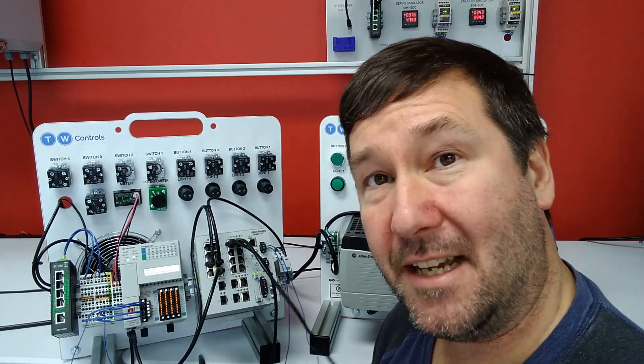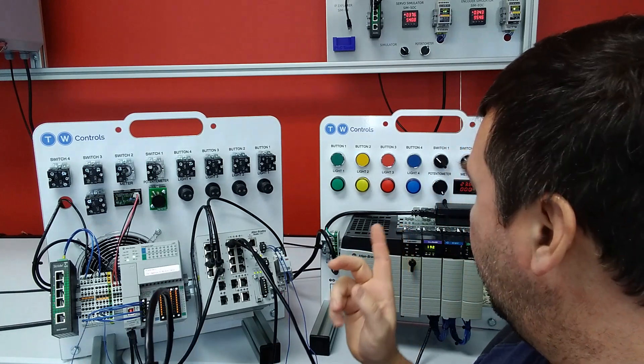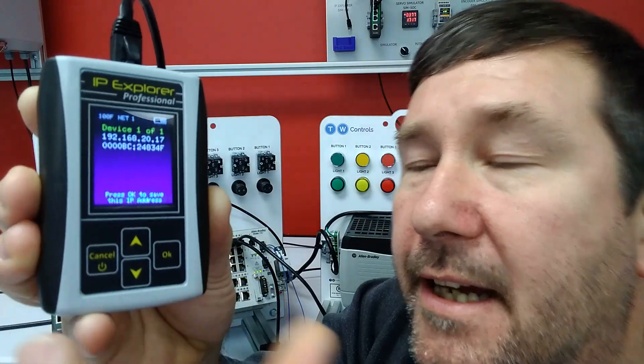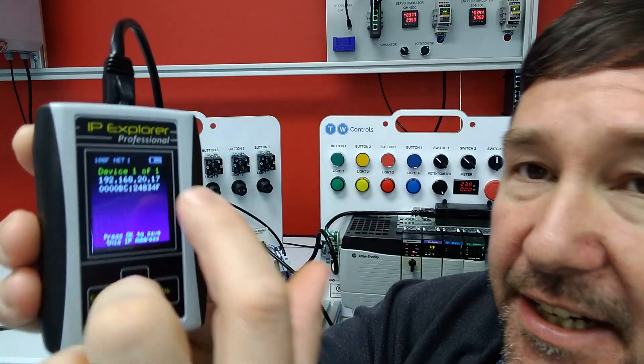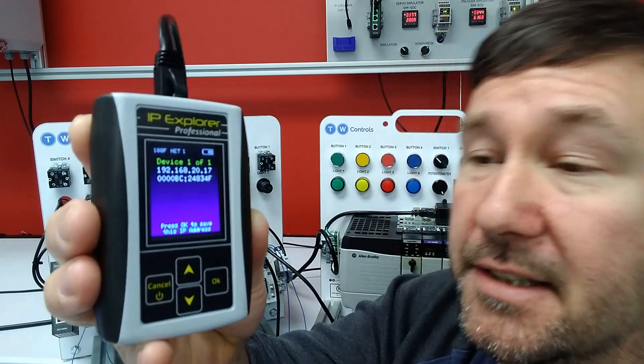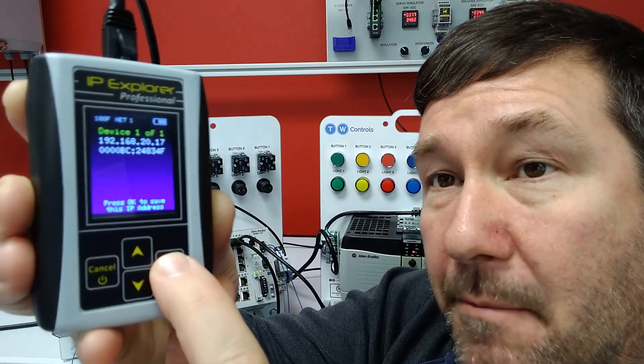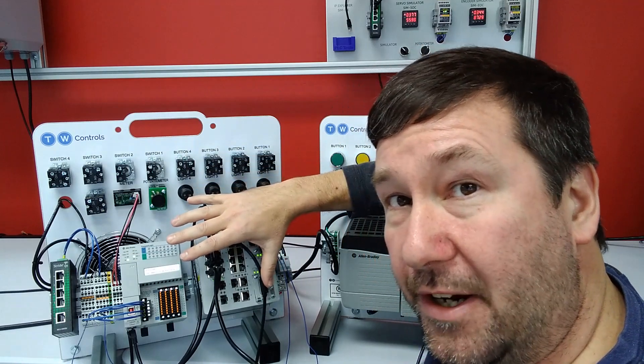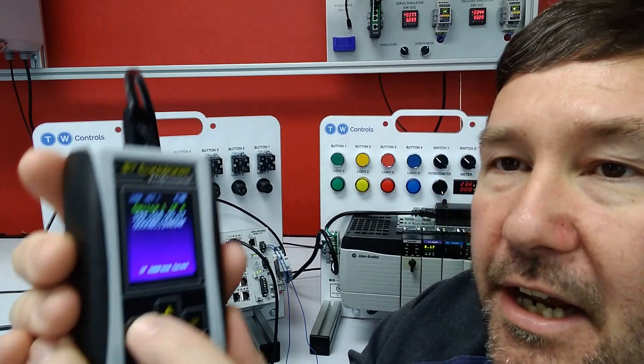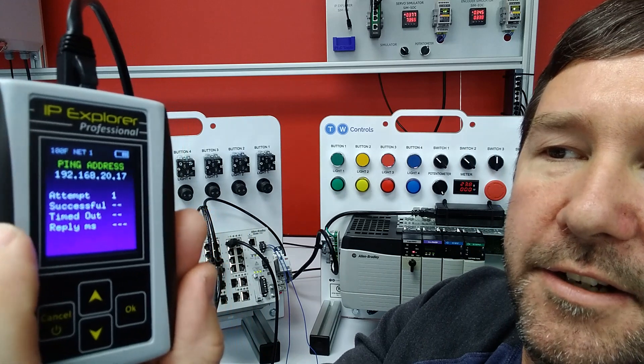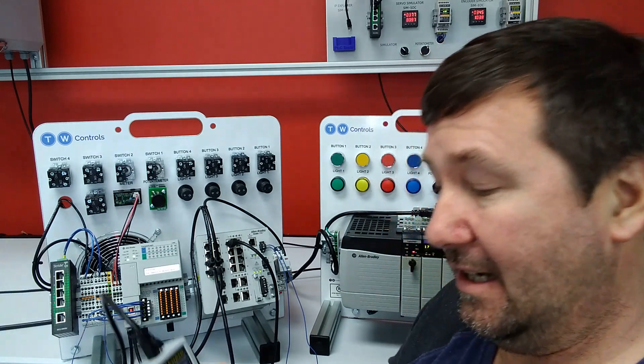So next, let's take this a step further and let's understand what the default gateway does. So we're going to try to ping, you know, let's try to ping this from this one's network. So we go back out. And well, first, let's read unknown on this one. This is kind of a neat deal. And while we are configured for an IP address of 192.168.10.2, we can still discover devices on other addresses. And what I'm going to do is I'm going to hit the OK button. And this is going to save it to the target IP. So I'm going to be ready to ping it now. And what I'm going to do is I'm going to go back to network 10. So we are now on the network of this CompactLogix trainer. We are not on the network of the ControlLogix trainer. And if I go to ping, then we're going to get attempts. And you're going to see that they're going to time out.